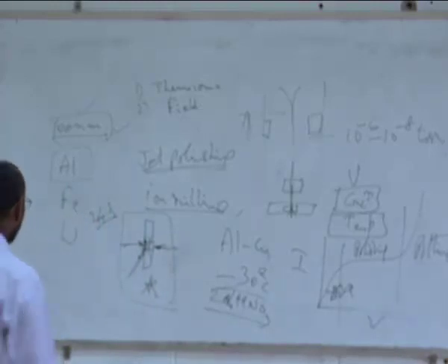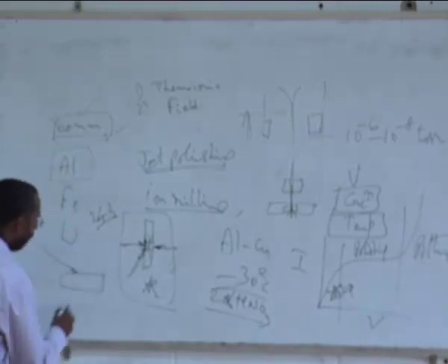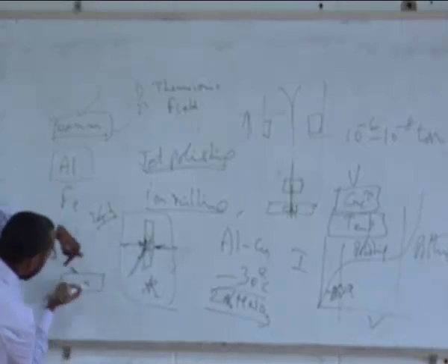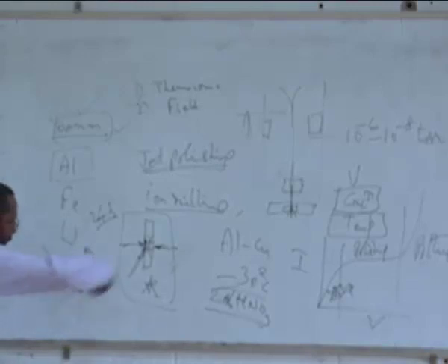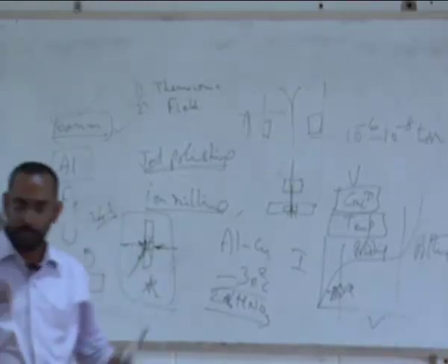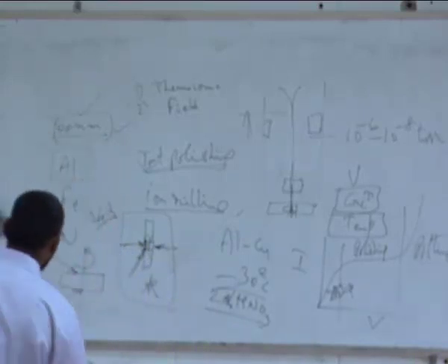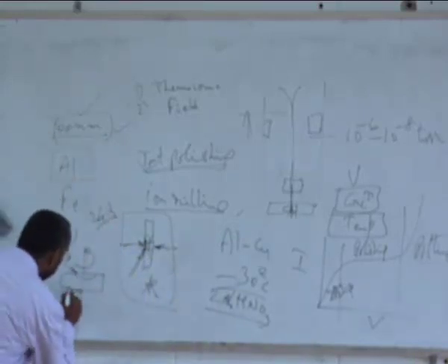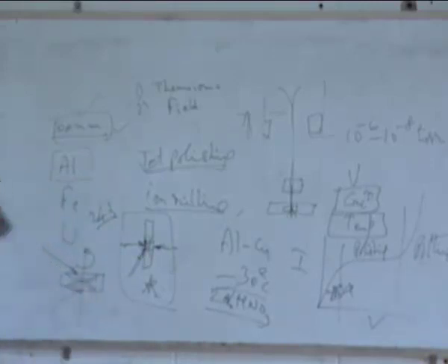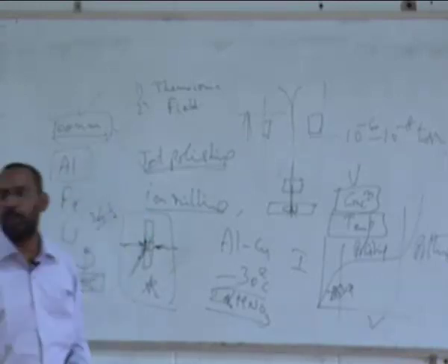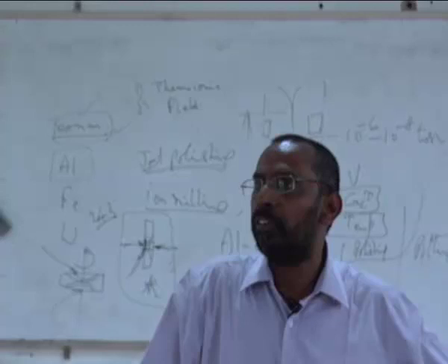You keep the sample horizontal and allow the beam to fall at an angle and keep rotating the sample around this particular axis so that the sample is being dissolved or sputtered away atom by atom, and in the process you see the sample starts from both sides becoming like this, and finally at some stage there will be a hole formed. Again a similar principle, that the hole is detected by a photocell and the machine is allowed to stop.